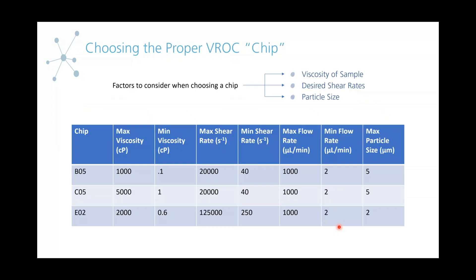You always want to make sure you're using the correct VROC chip for your measurements. Some things to consider when deciding which chip to use are: what is the viscosity range of your samples, what desired shear rates do you want to test at, and what are the particle sizes of your samples. For example, the B05 chip has a max viscosity of 1,000 and you can go up to a max shear rate of 20,000. But if you wanted to go at a higher shear rate, you'd want to use something like the E02 chip. The B05 also has a max particle size of 5 microns, while the E02 only has 2.